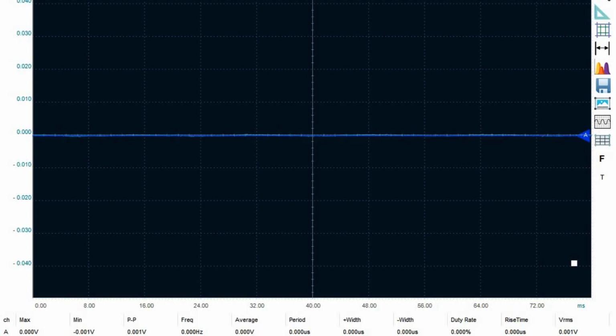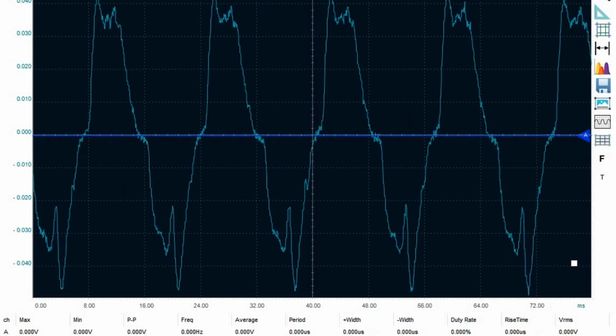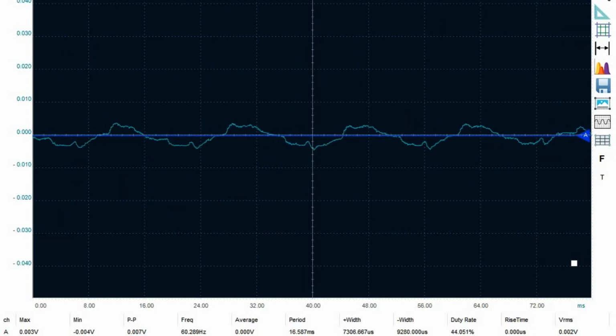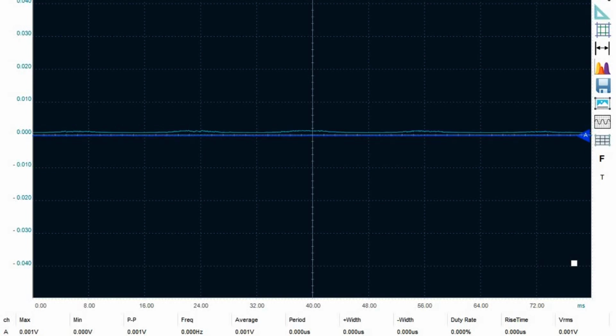Yep, peak to peak, actually here it's flashing between 0 and 1 millivolts. So I would say that's the quietest side, although it did stabilize at 1 millivolt. So I'm going to switch this back again, and it's still showing 1 millivolt, but it's fluctuating between 0 and 1. The resolution on this scope is not that good, so I'm going to say that I've got the ground lead on the quietest side. That really is a guess.